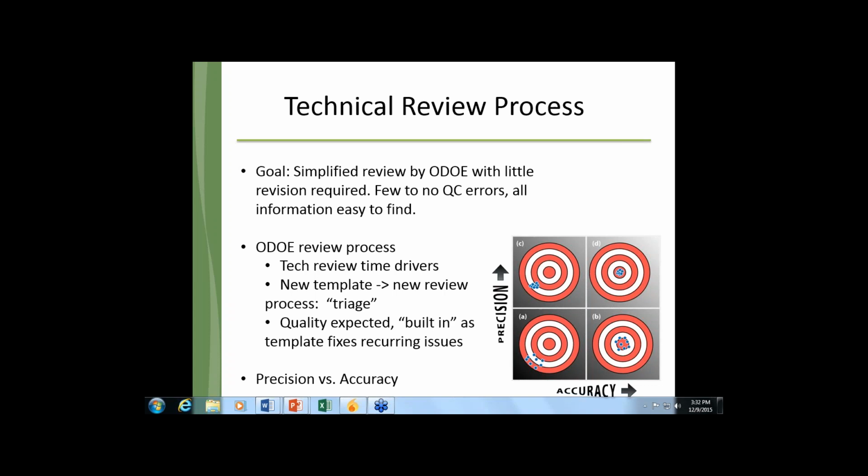When we go to the level of detail of the EEMs, we already know what the key EEMs are. I'm probably not going to look at the onesie-twosies, but I'm going to look at the ones that are driving most of the energy savings. Does it make sense? Does it tie back to the overall description of the envelope or the energy using systems? Yes, it's all check, check, check. Now I've got a good feeling. Everything's documented every time I go from front to back to look at more detail or less detail. It all hangs together. I can find my calculations. I know what the assumptions are.